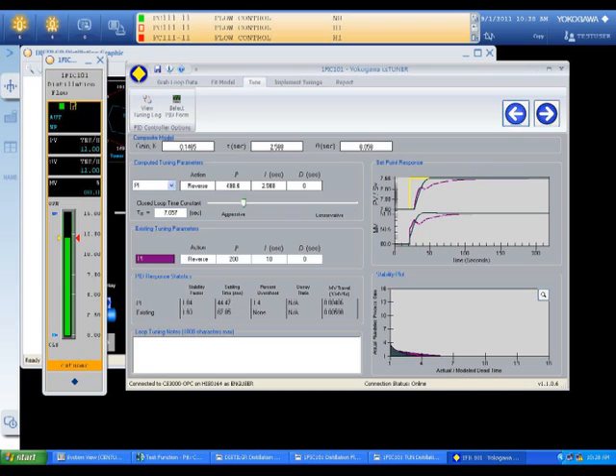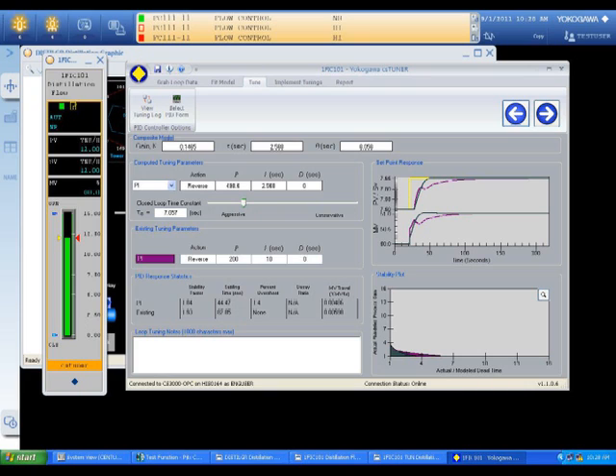Moving to the next tab, the software then calculates tuning constants and displays the new proposed constants along with the current constants. A dynamic plot and slider allow the user to make the control action more aggressive or more conservative before implementing the change in tuning.